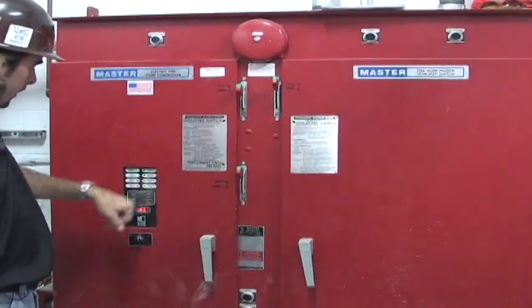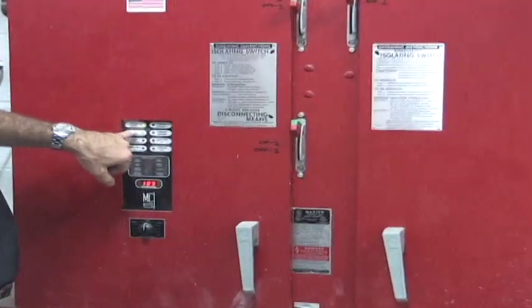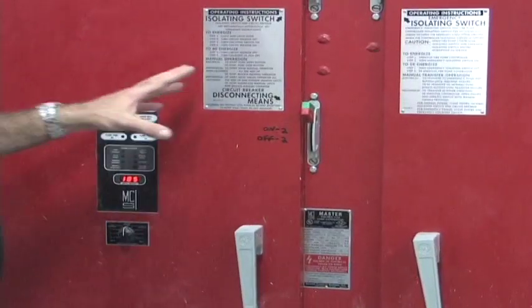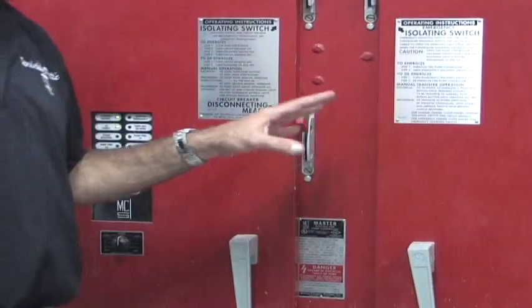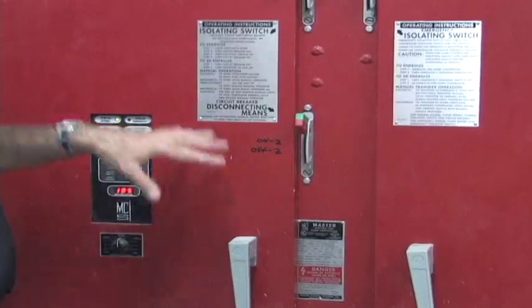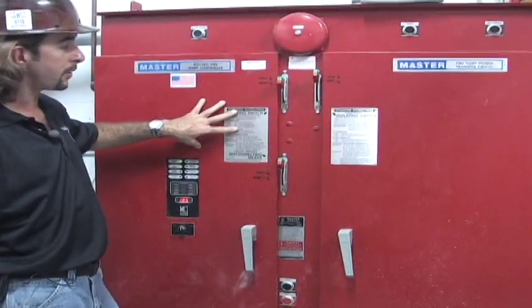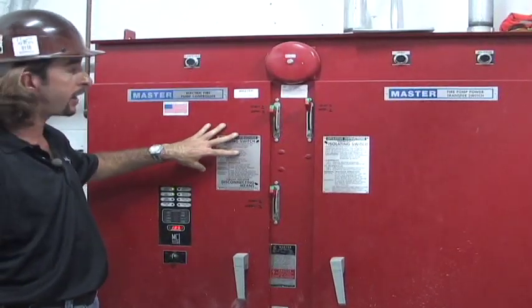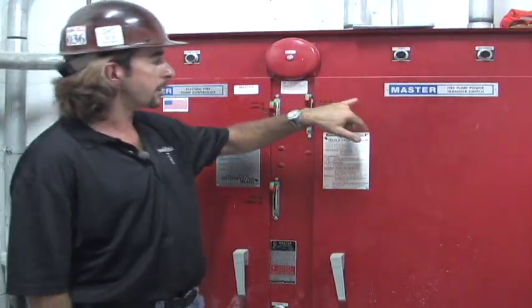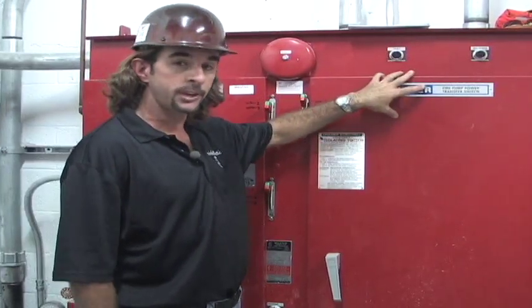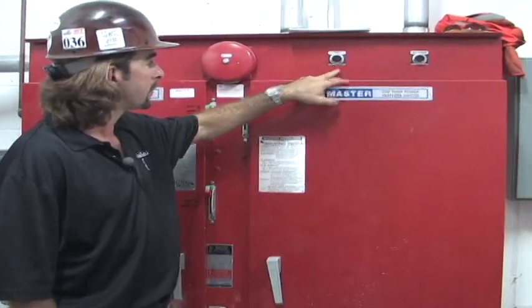We have a clean screen here, just the green lights. We're going to start the fire pump with a loss of pressure. We're going to run some water out one of the main drains. It's going to start automatically off a loss of pressure. And what we're going to do is the manual trip of the transfer switch. We have a test button right here.